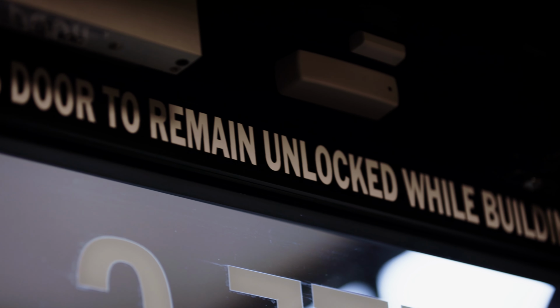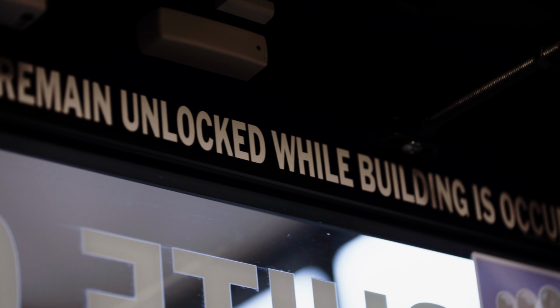We must verify that if it is able to be locked from the egress side, which is our interior side moving outward, then there must be a sign that says must remain unlocked while building is occupied. And if there is any type of lock present, like a chain or a padlock on the egress side, then that should be noted in the inspection because those doors must be openable in the event of an emergency.